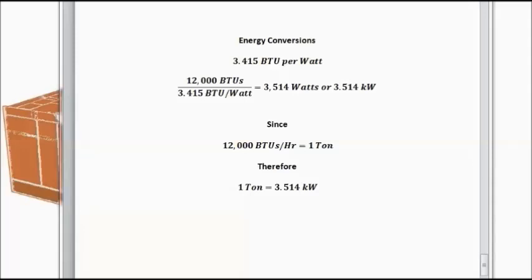as there's 12,000 BTUs in a ton, and divide that by 3.415, we get 3,514 watts, or 3.514 kilowatts. And again, since 12,000 BTUs per hour is equivalent to 1 ton of refrigeration, we can say that 1 ton is the equivalent of 3.514 kilowatts.